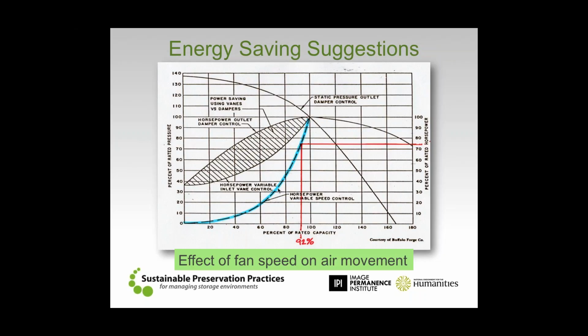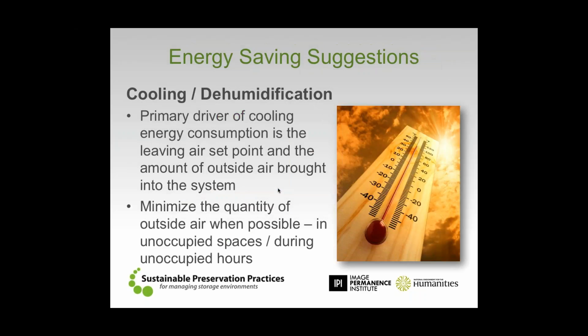So for those days when it's not a peak condition, where it's not the absolute hottest or the absolute coldest, we don't need the system to do 100% of what it's capable of. Oftentimes we can reduce that percentage of operation by some quantity and still achieve exactly what we're looking for in terms of space conditions. When we're thinking about cooling and dehumidification, the two things that really come into play here are, first, what is the leaving air set point off of the cooling coil? In other words, what is the temperature the coil is trying to achieve?